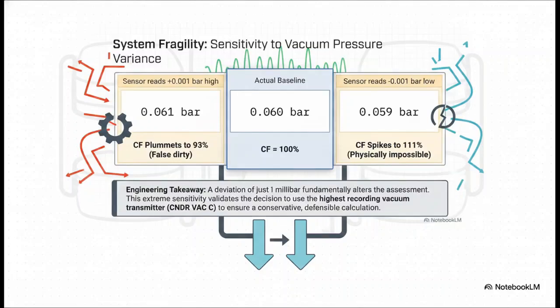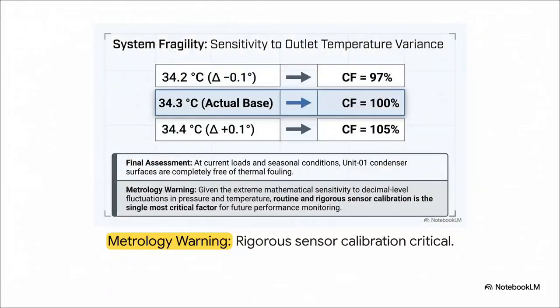This extreme fragility totally validates our earlier decision to use the highest recording transmitter just to stay conservative. And guys, this fragility applies to temperature as well. A mere 0.1 degrees Celsius variance in our cooling water outlet temperature swings the entire plant's cleanliness assessment by several percentage points. So while our final assessment is that Unit 01 is completely free of thermal fouling, I really want to leave you with this metrology warning. Given this extreme mathematical sensitivity, routine and rigorous sensor calibration isn't just a good practice, it's absolutely the single most critical factor for future monitoring. All of our beautiful thermodynamic math is completely useless if we can't trust the sensors feeding the pipeline.